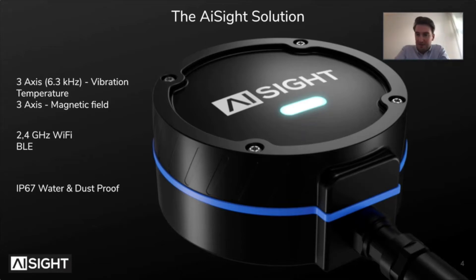If the machine is changing, we do a full analysis and understand the root cause of the problem. For example, with typical equipment like an electric motor, the sensor identifies whether there's a bearing fault, an imbalance, or another type of problem on the machine. Based on the type of error identified, we can see what state the error is in and whether it's developing over time. If it is, we can also estimate roughly how much time is left until the machine will completely break down, helping customers better plan their maintenance and improve quality control processes.